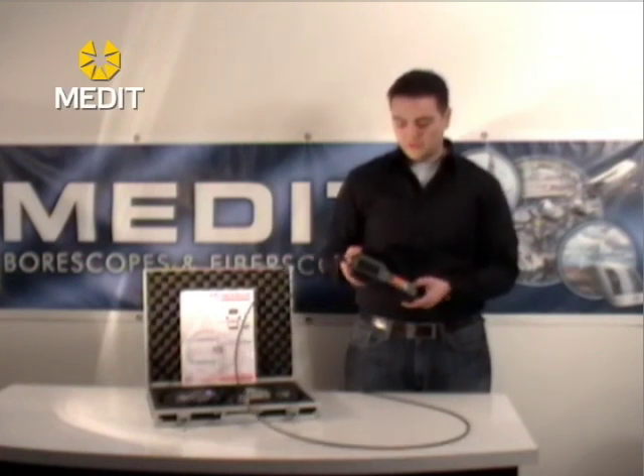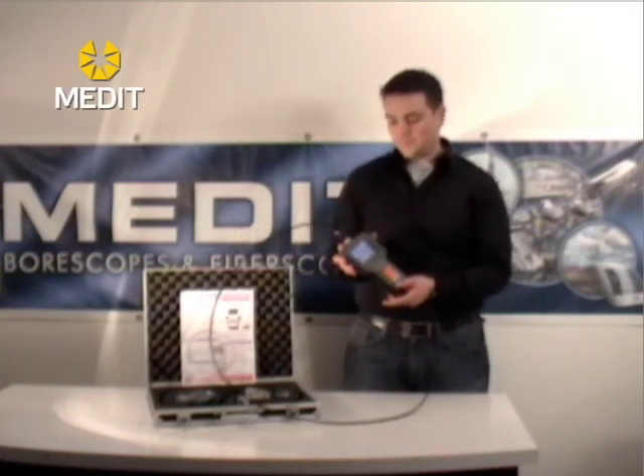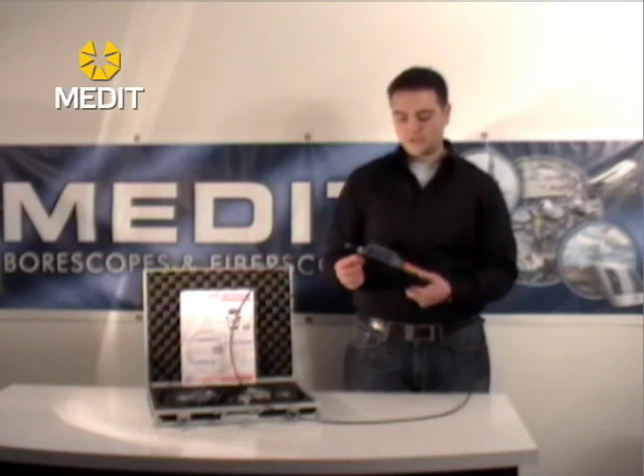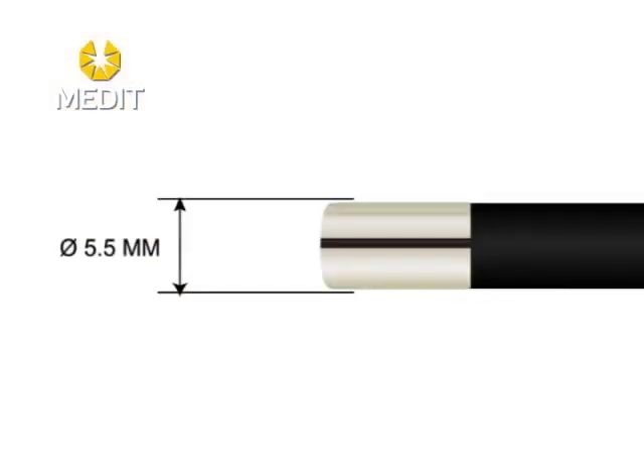In order to use your monitor unit you're going to want to turn the power on. Place your inspection probe into your inspection area without bending the camera chip which is right in the tip. We've had to reinforce these with stainless steel because sometimes the tip will bend and that can easily destroy the CMOS camera that's inside the tip.